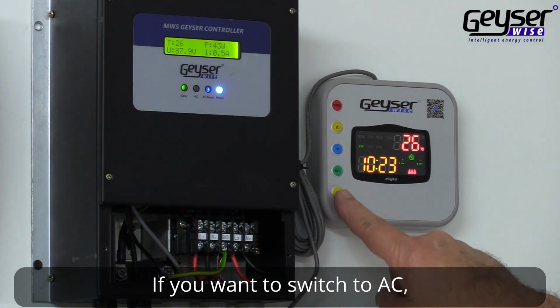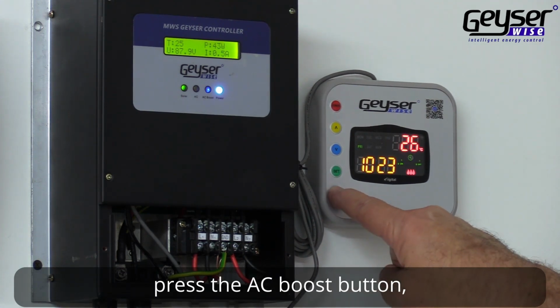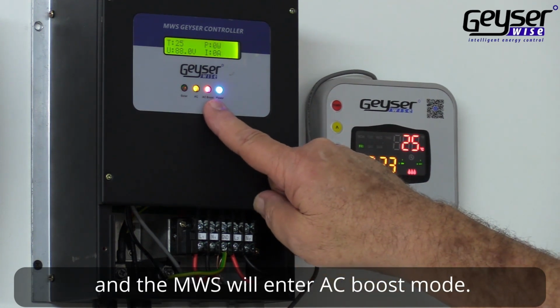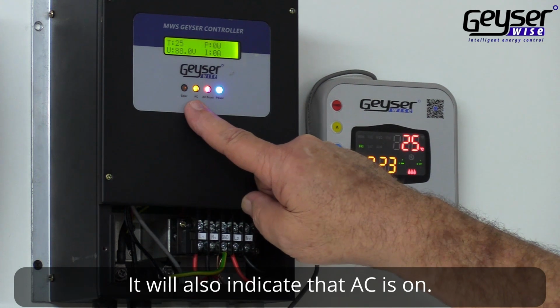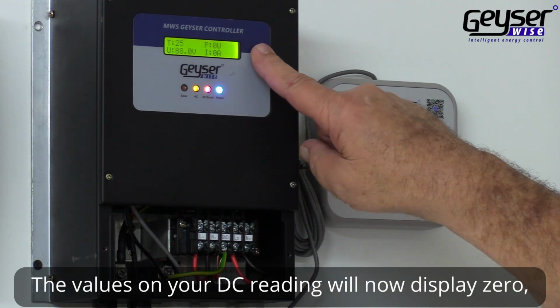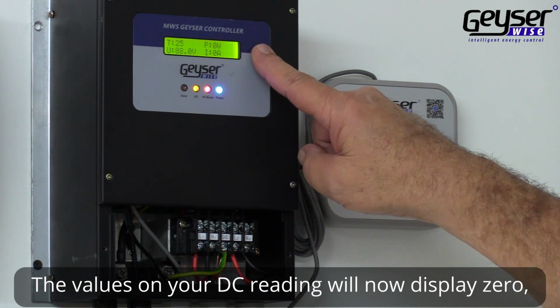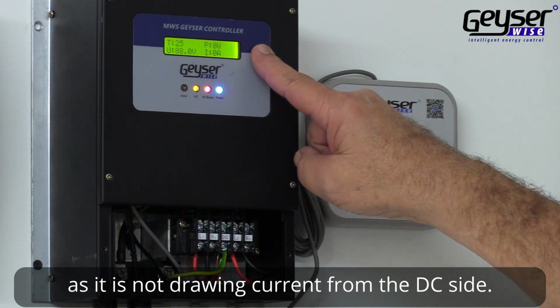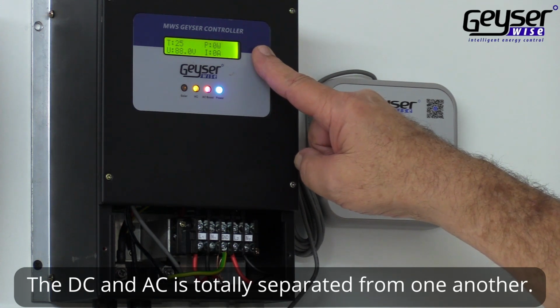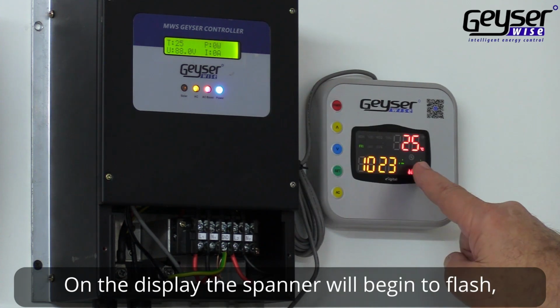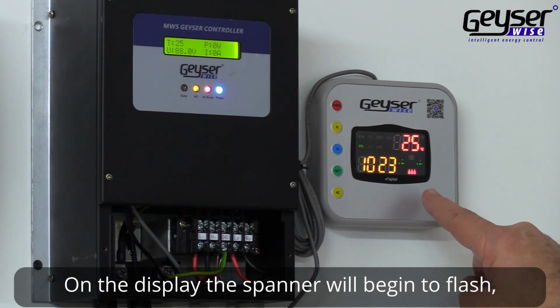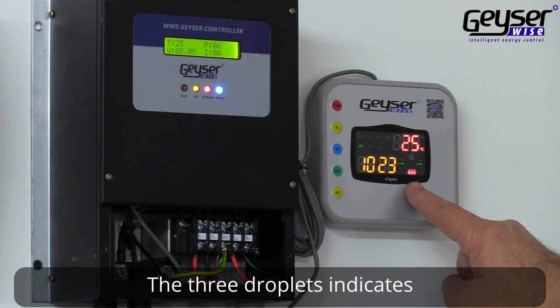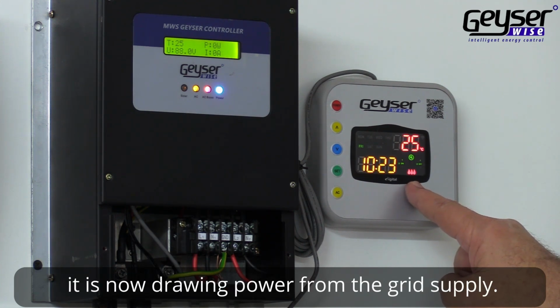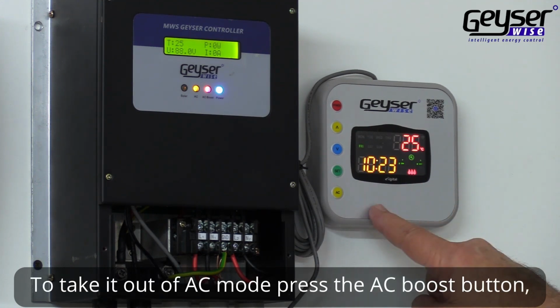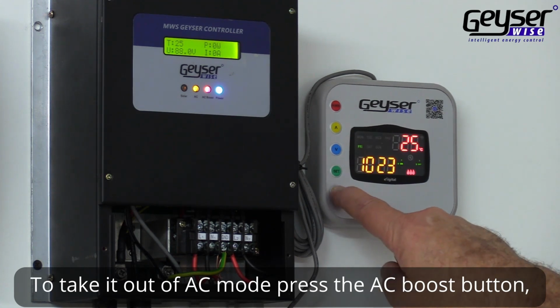If you want to switch to AC, you can press the AC boost button and the MWS will enter into AC boost mode. The MWS will display that AC mode is on, and the values on the DC side will now read 0. This is due to it not drawing current from the DC side. The AC and DC are completely separated from one another. On the display, the spanner will begin to flash, indicating that the system is in AC mode. The 3 droplets indicate that the system is now drawing power from the grid supply. To take the system out of AC mode, press the AC boost button.